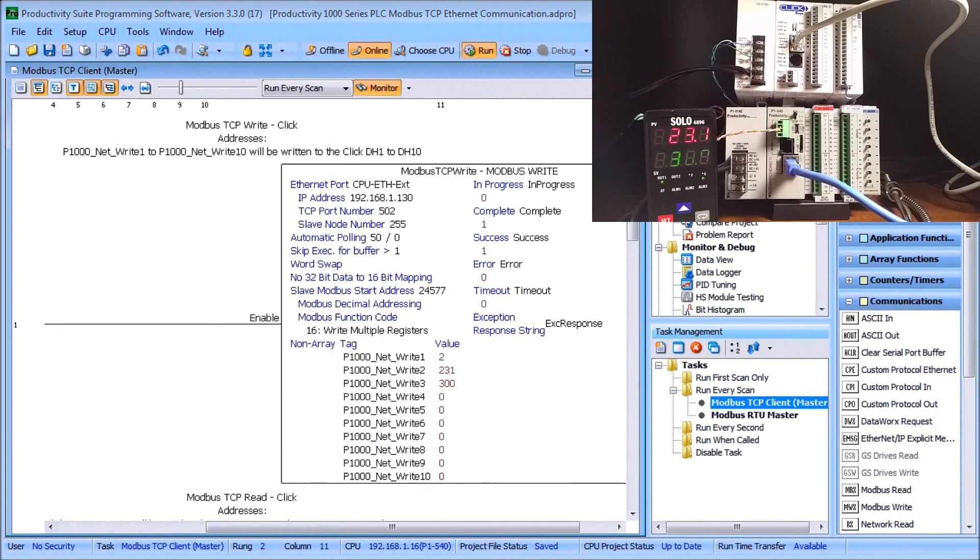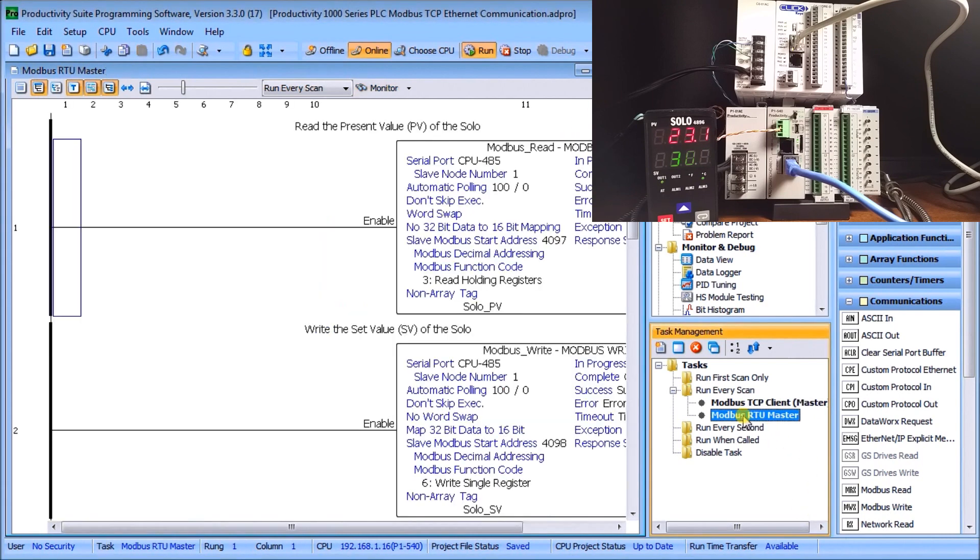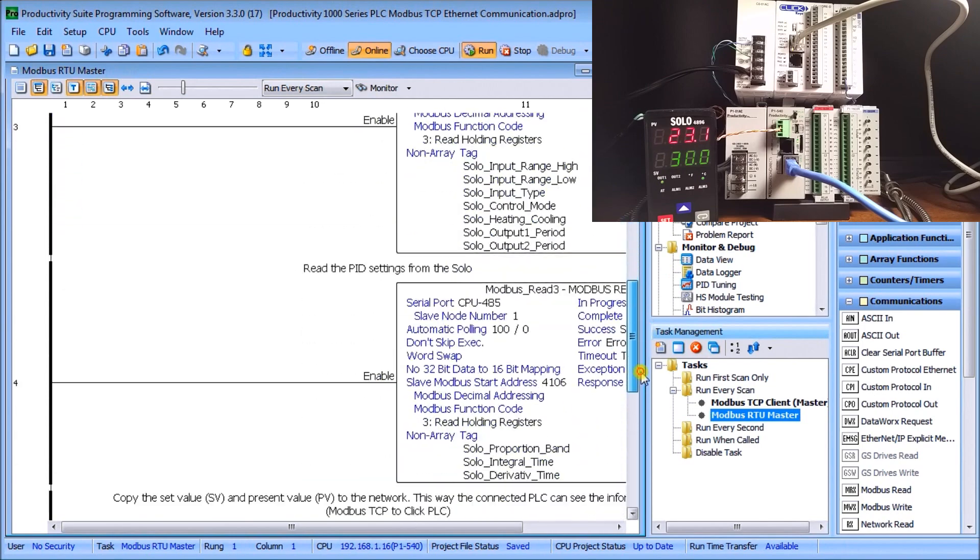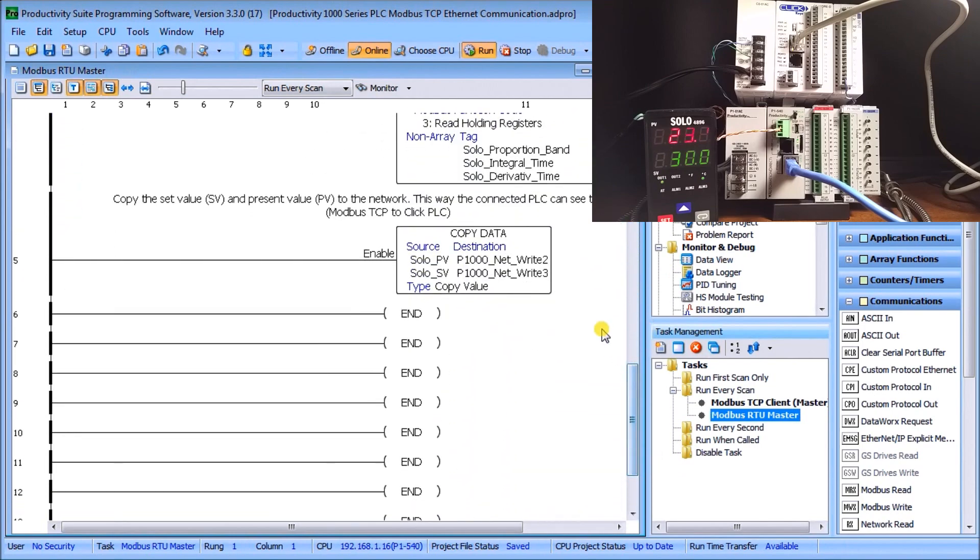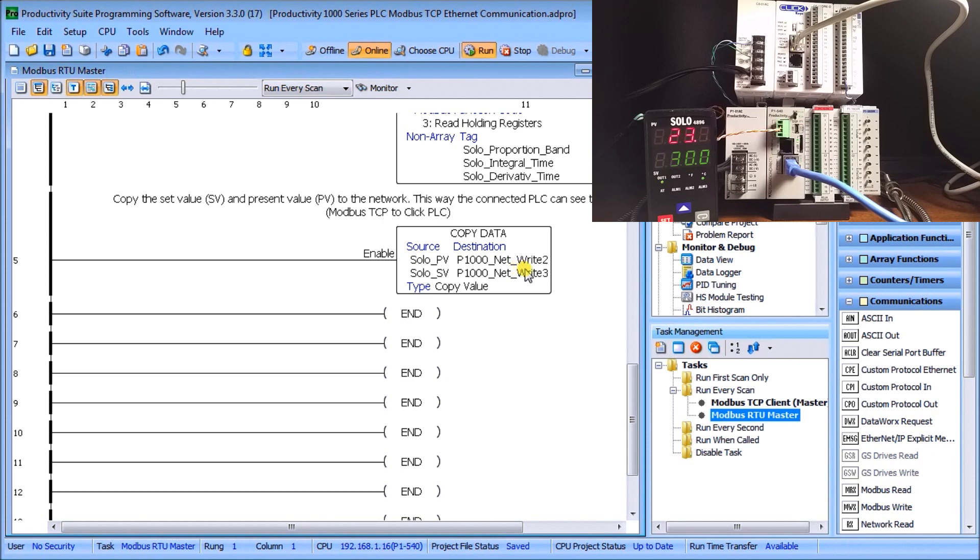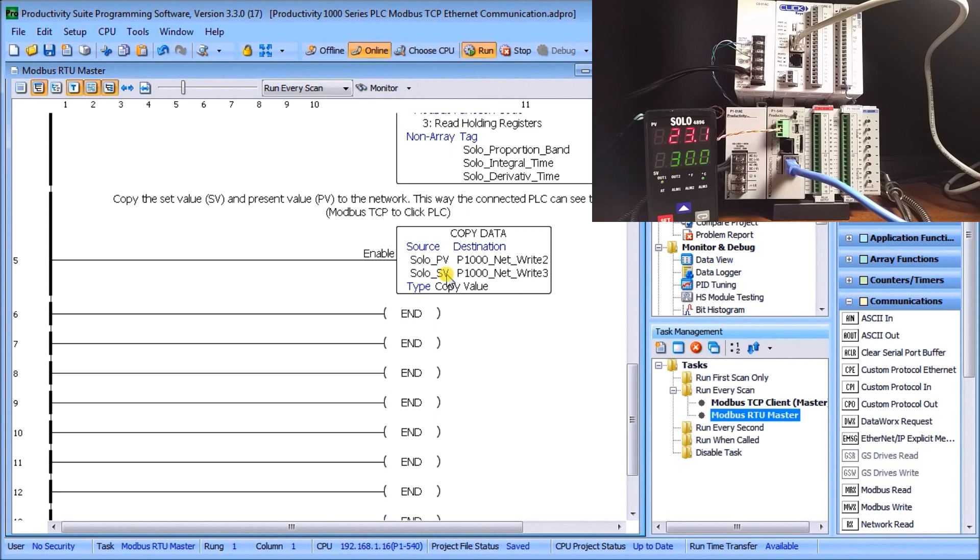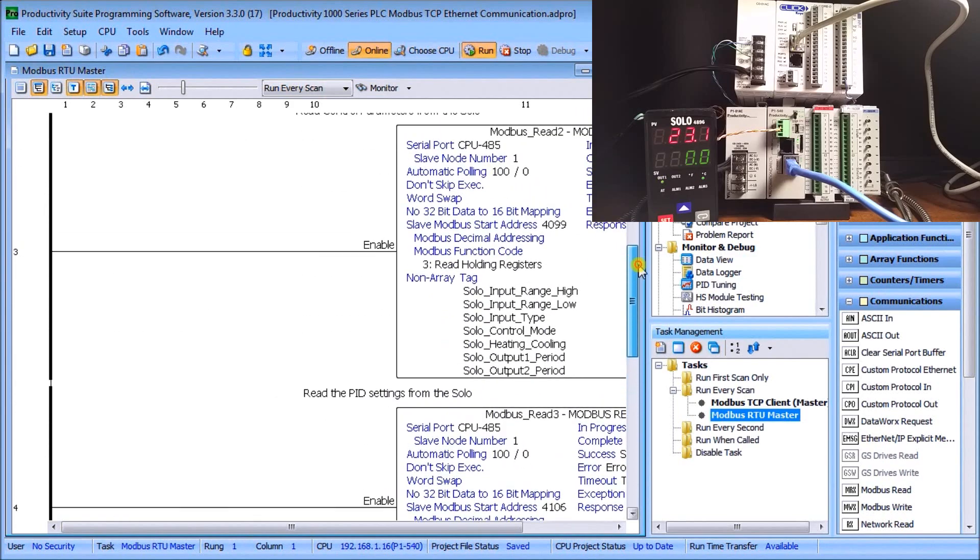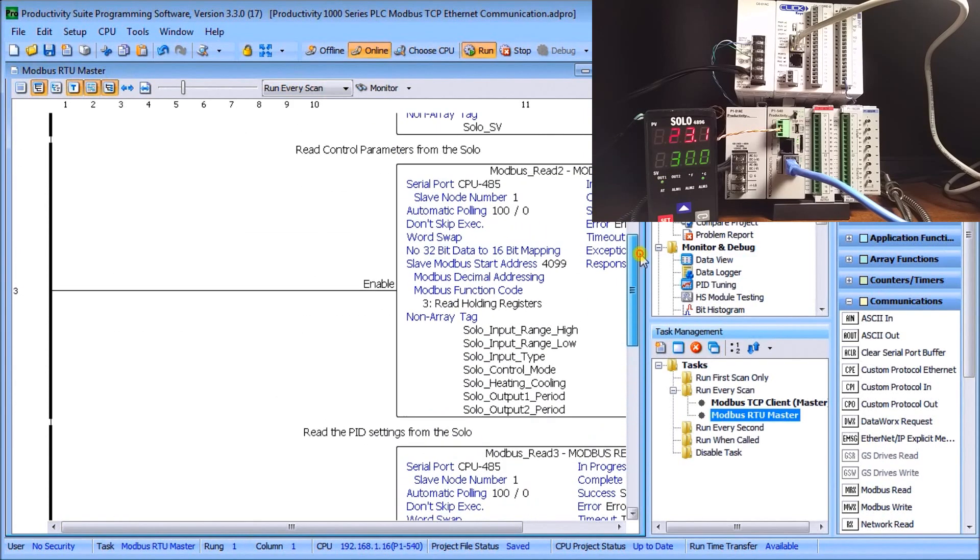Let's close that down and we'll go back to our Productivity. On the Productivity you'll notice that we have our Modbus RTU Master. If we go down to the bottom, this is the master that we created before. What we do is we're copying the SOLO present value into NET_WRITE_2 and NET_WRITE_3 as our set value. So one instruction, we start putting things up on the network between these two controllers—very quick, very easy in order to communicate back and forth.